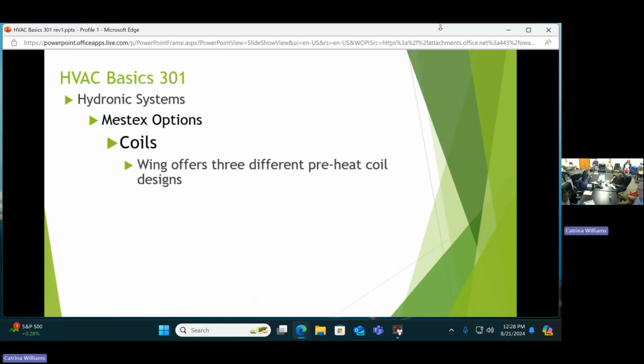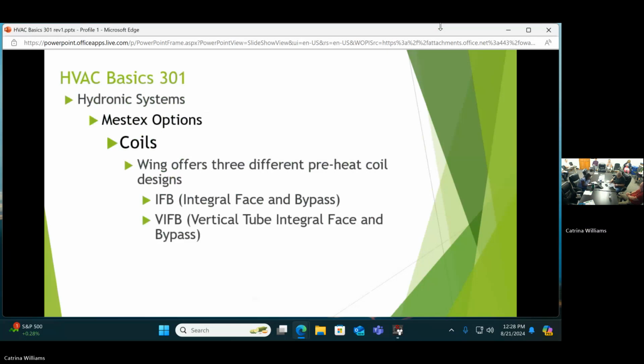So on the coils, we offer three different types of coils that we get into for LJ Wing. The IFB, and that means integral face and bypass. We'll show you some pictures here in a couple slides to see what that does. That's a horizontal coil, or horizontal tubes, in that particular one. We have a VIFB, which is the same concept, but those tubes are running vertical now. And lastly, there's the MV. MV stands for multiple vertical tubes. We have multiple headers in that series. And that's again a vertical, like I said before.